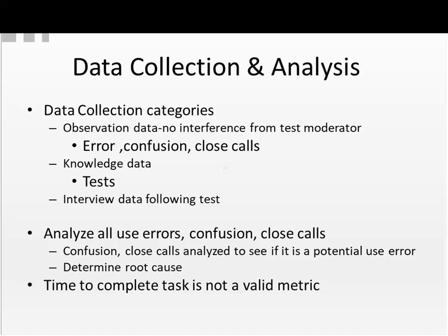And then there's interview data, where you ask the participant questions. You should analyze all use errors, confusions, close calls. You don't want to restrict your analysis to the errors, failures. And determine the root cause for all errors, confusions, close calls.